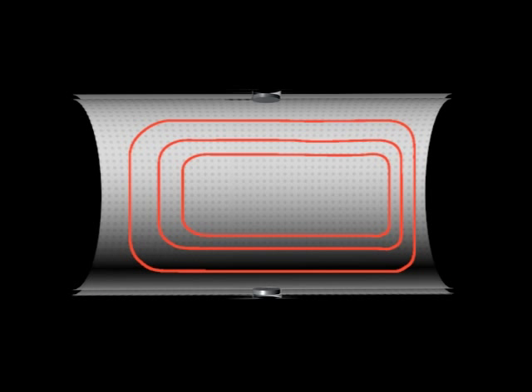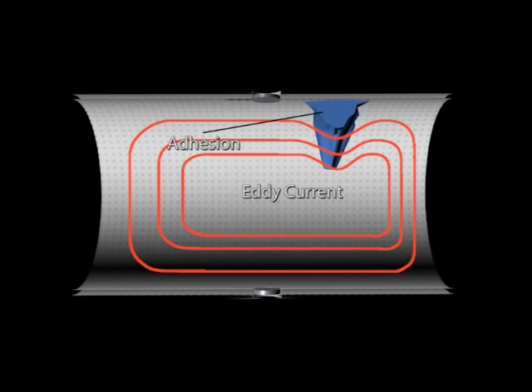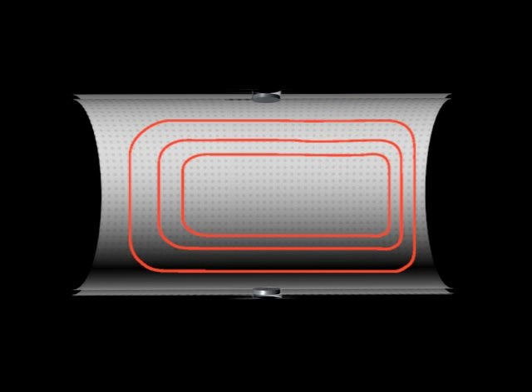Induced noise is generated by eddy currents in the conductive process liquid in the tube. When conductors, such as the liner or process fluid, are exposed to changing magnetic fields generated from the coil's electromagnetic drive, eddy currents will be induced in the conductors. Eddy currents create induced magnetic fields, which oppose the change of the original magnetic field generated by the coil drive. This is called electromagnetic induction.